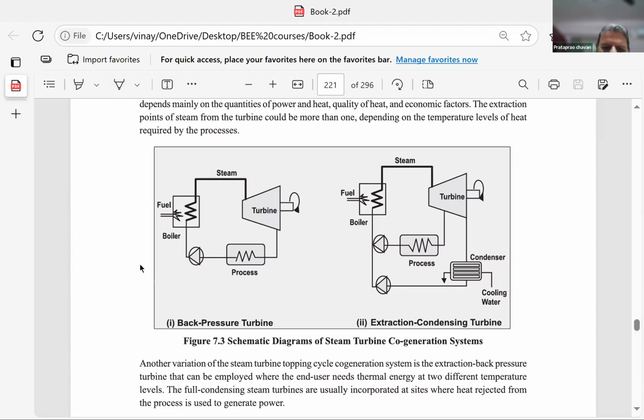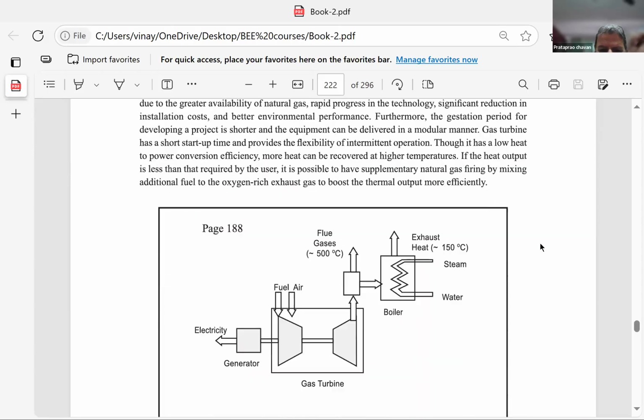So these are two methodologies. One is the purely back pressure turbine. It is not allowed to exhaust into a condenser. Heat is fully recovered in the back pressure turbine. So wherever your mechanical power requirement is more than the electrical component, we use this system. The back pressure turbine system is the most efficient mechanical power system with the same amount of fuel. Here the efficiency slightly goes down, but it can give you better power output and lesser output for the process, right? Then there are other possibilities also.